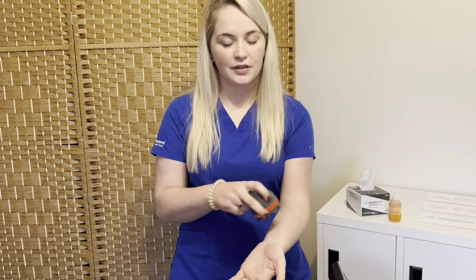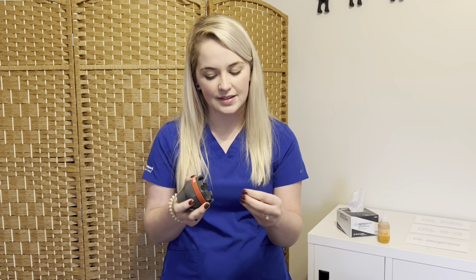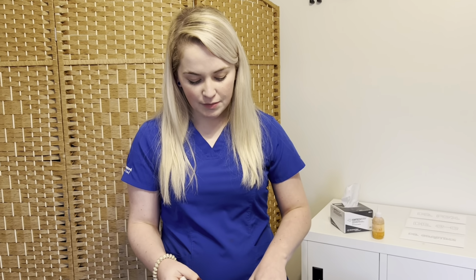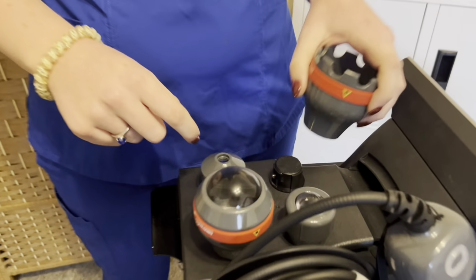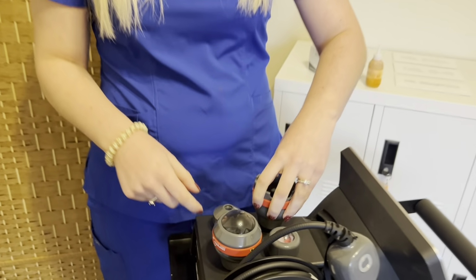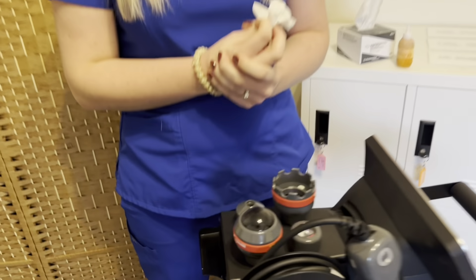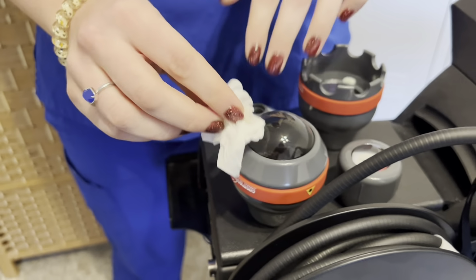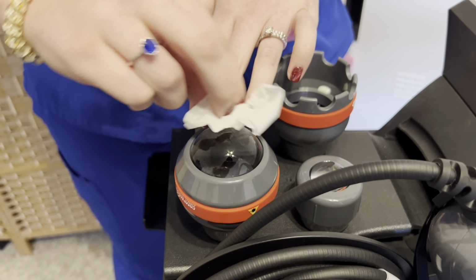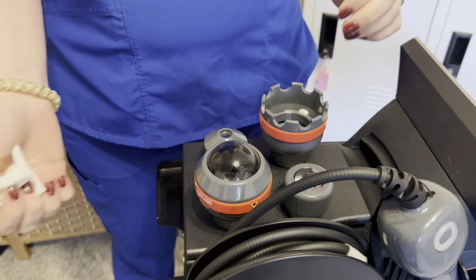So, especially with these non-contacts, it's important. It's called a non-contact head for a reason. We want to make sure that we're hovering over the surface. We're not getting into the hair of the animal, because when you hit the hair, all the debris and dirt goes back up into these lenses. When you're using a contact treatment probe, you can touch the surface of the animal with it, but it is imperative that once you are done, you are wiping down these treatment heads accordingly with a Kimwipe and alcohol. Let me show you an example. So Kimwipe, alcohol, rubbing down the treatment head appropriately, getting all that dirt and debris off, and then you're good to go for your next treatment.